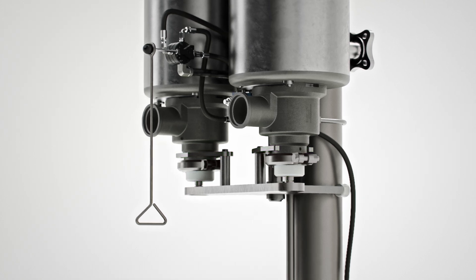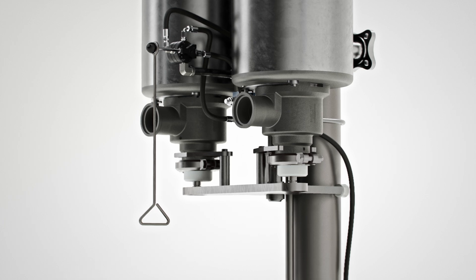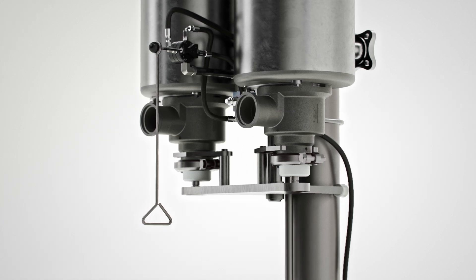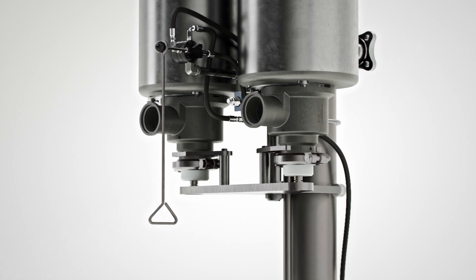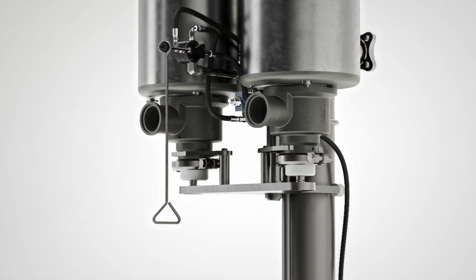For cleaning, inspections, and routine maintenance activities, the dual cylinder foot assembly is positioned underneath the heat exchangers with the alignment pins seated and holding arms in position above the bearing clamps.